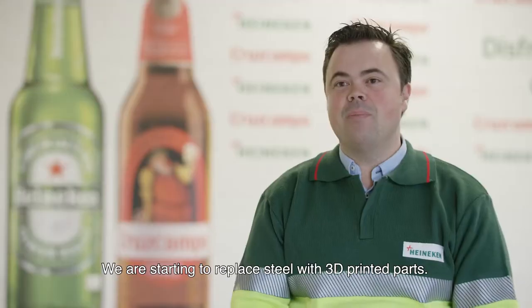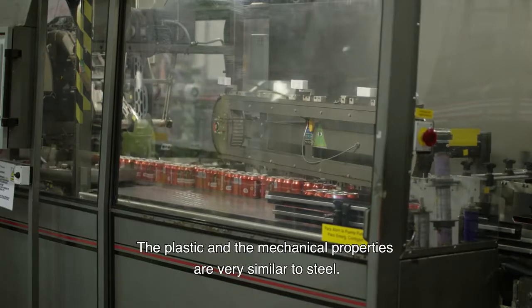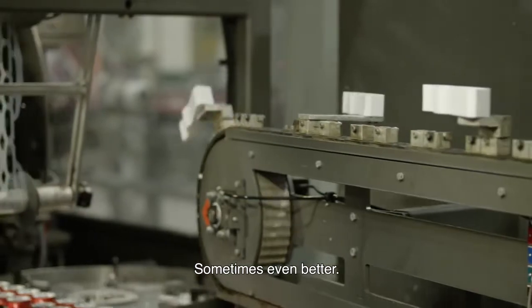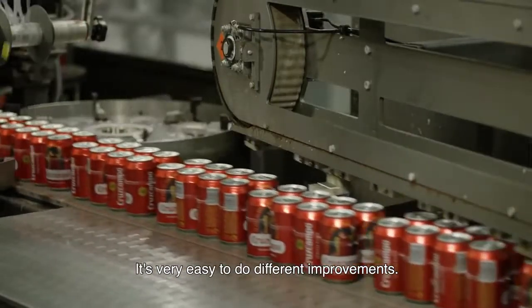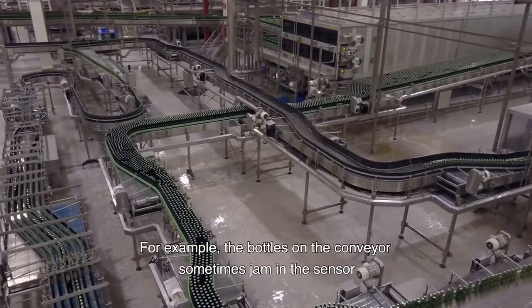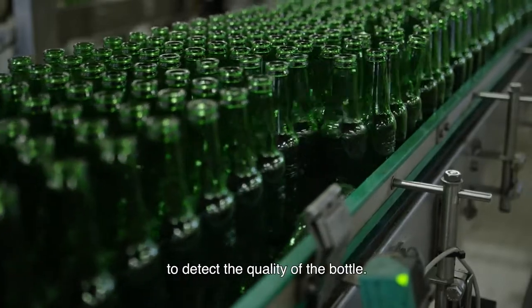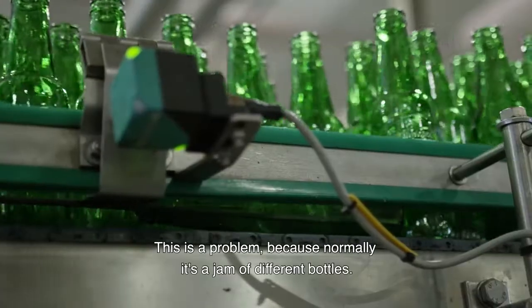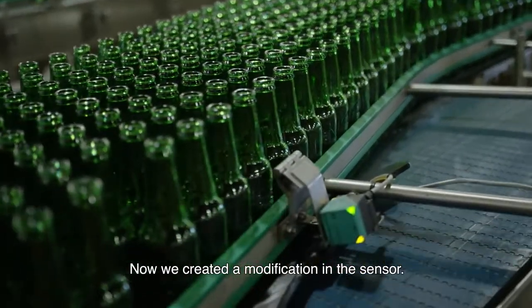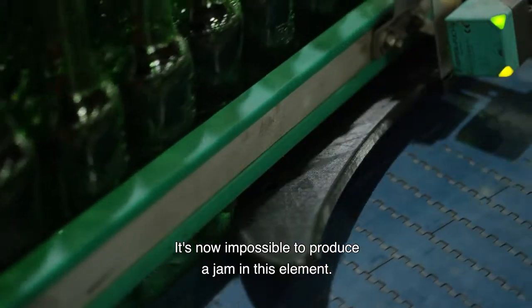We are starting to replace steel parts with 3D-printed plastic components. The mechanical properties are very similar to steel — sometimes better. It's very easy to make different improvements and reduce material weight. For example, bottles around the conveyor sometimes jam in the sensor that detects bottle quality. We created a modification on this sensor to make it impossible to produce jams in the line.